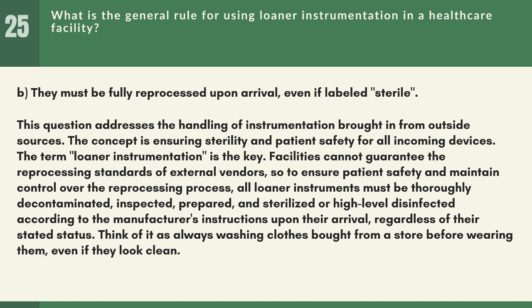This question addresses the handling of instrumentation brought in from outside sources. The concept is ensuring sterility and patient safety for all incoming devices. The term loaner instrumentation is the key. Facilities cannot guarantee the reprocessing standards of external vendors, so to ensure patient safety and maintain control over the reprocessing process, all loaner instruments must be thoroughly decontaminated, inspected, prepared, and sterilized or high-level disinfected according to the manufacturer's instructions upon their arrival, regardless of their stated status. Think of it as always washing clothes bought from a store before wearing them, even if they look clean.